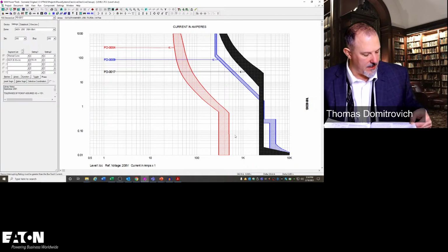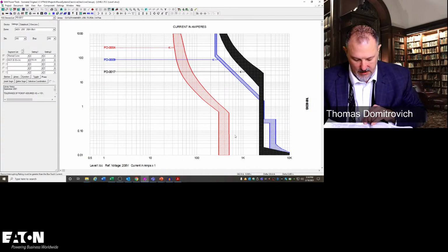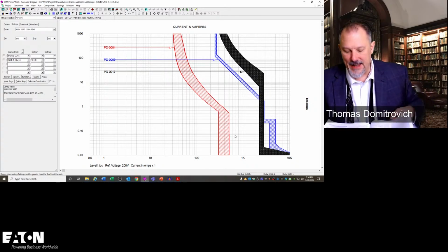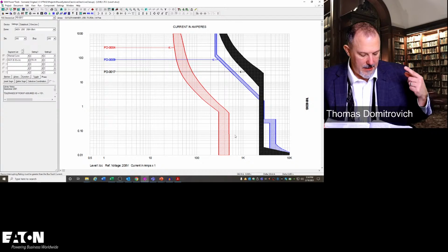It says 700. The life safety branch of the essential electrical system shall meet the requirements of Article 700, except as amended by 517. And it says 700.32, which is selective coordination, shall not apply. Thank you. 517.31(G). Now that makes sense.